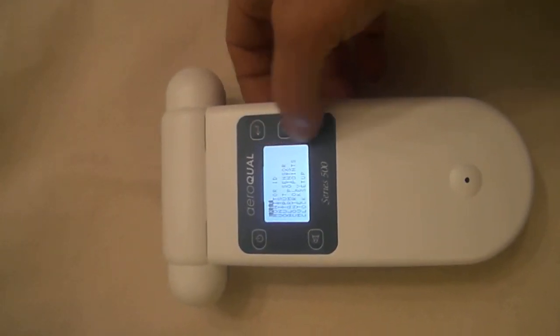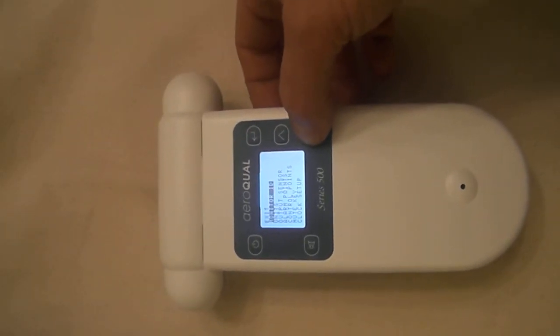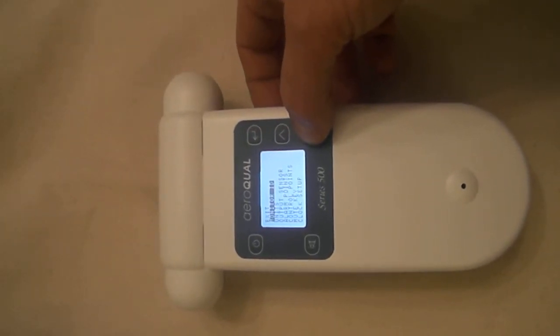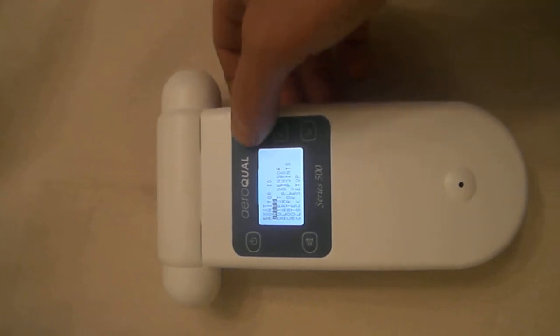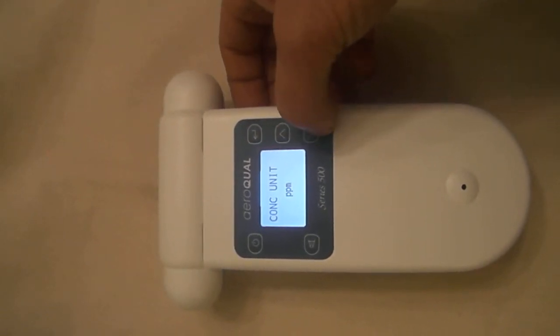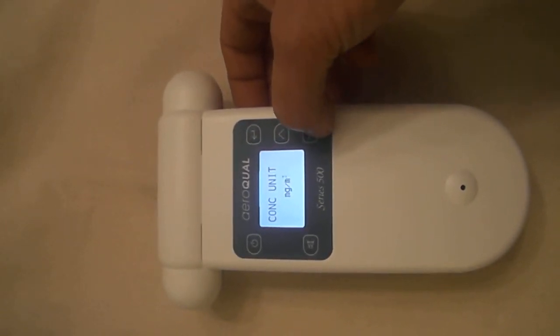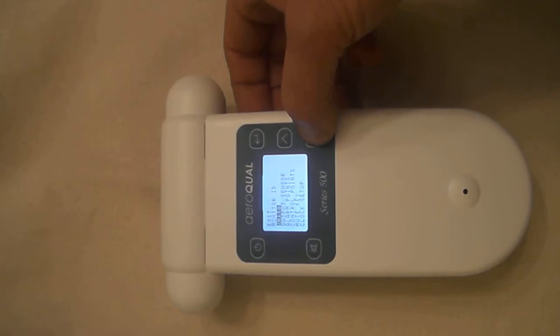You can also go into monitor setup. We can change the monitor ID if there's a series of these in line. We can change the units depending on the sensor head that you have.